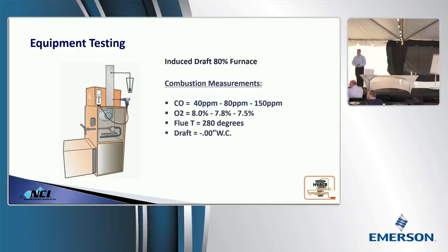The testing methodology: I have the privilege of doing ride-alongs with a lot of technicians, and they have been taught that you don't test any rush until steady state. Yep. They don't do startup or shutdown. They take the readings, they pull their analyzer, they log the data, and shut everything down. So it was important that we understand their NCI's testing methodology. Yep. As opposed to some of the more popular. Excellent point. You nailed it.